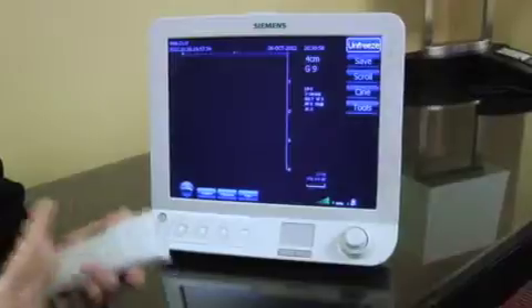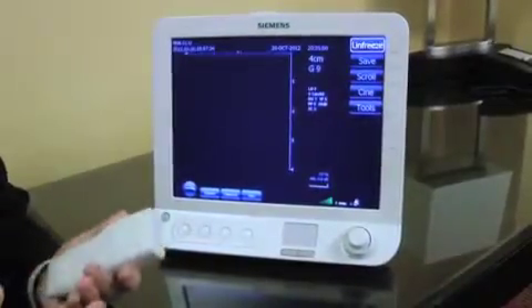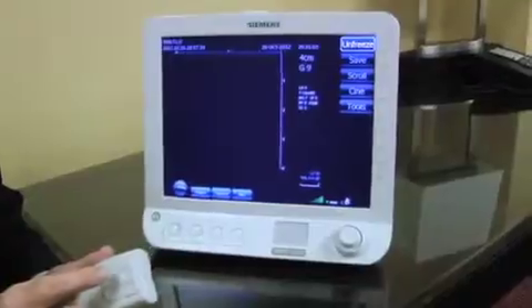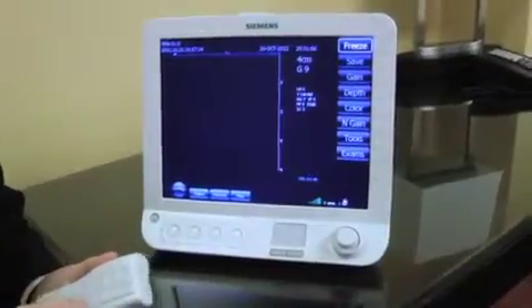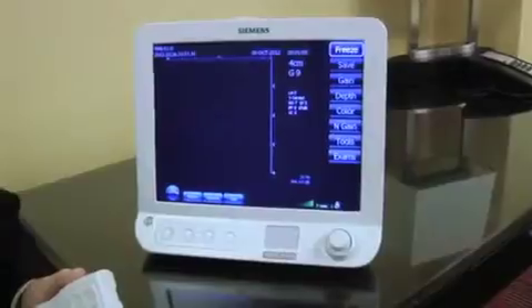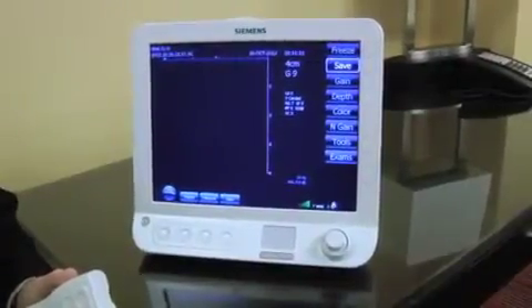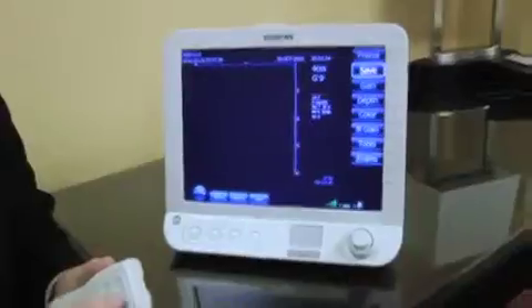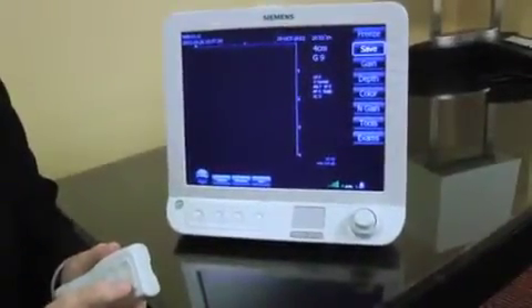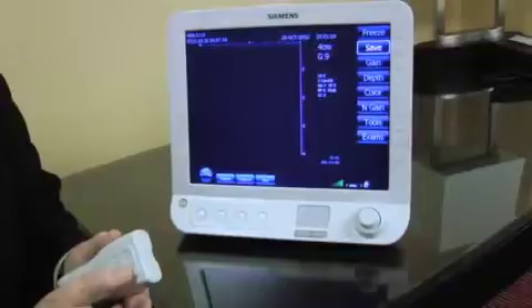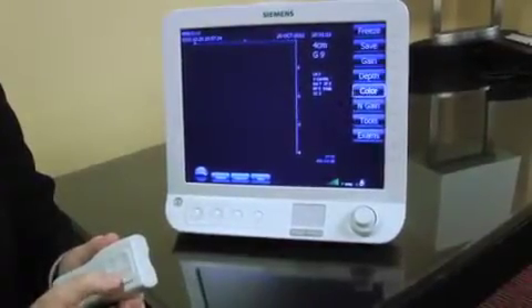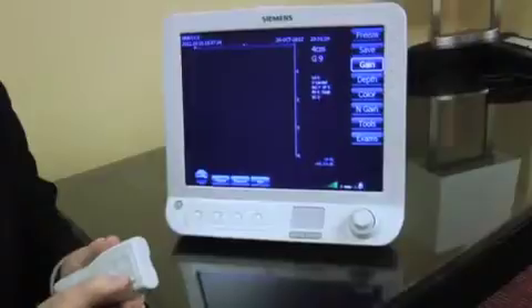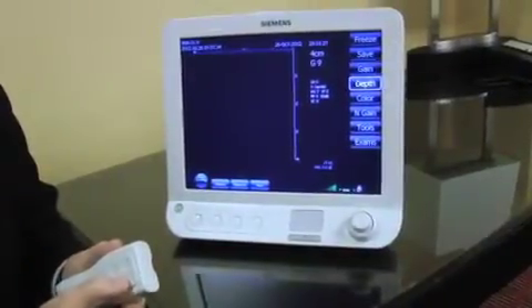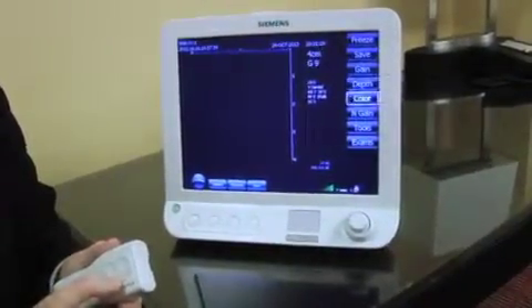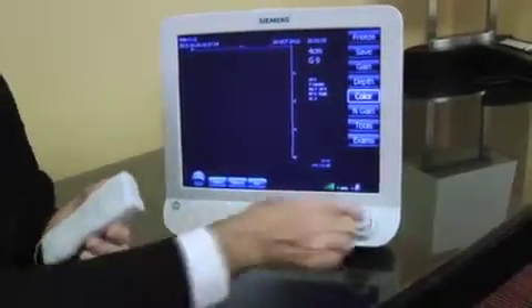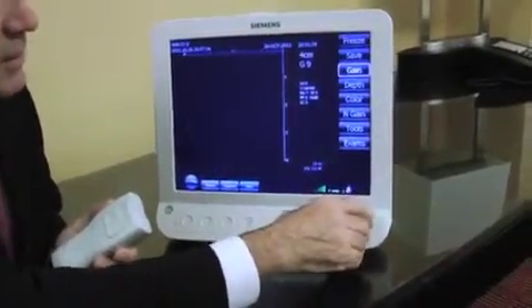So if I am set up, I'm ready to start scanning, and the system is frozen, I can do that from the probe. I unfreeze it, then I get my real-time controls. I can save. The system does digital saves. It's DICOM compliant. You can export in a DICOM format or in multimedia formats. And then we have large buttons for your basic controls up front, so things that you need to do even in this type of exam, change gain, change depth, turn color on and off, can be done from the probe as well as from the system if you have access to this system.